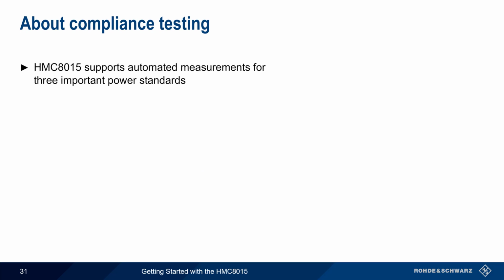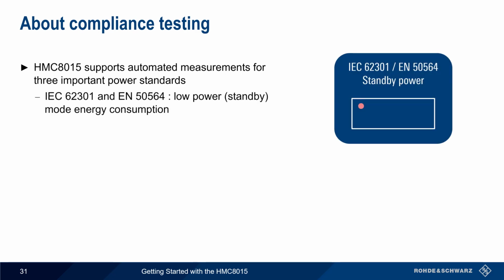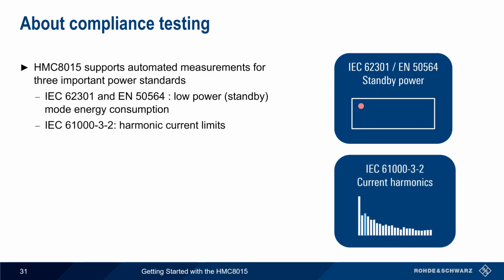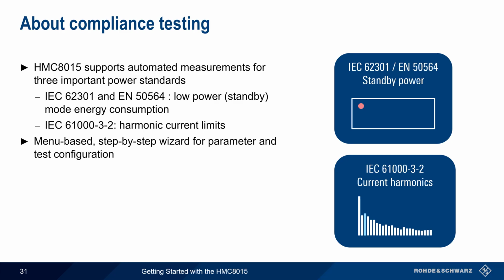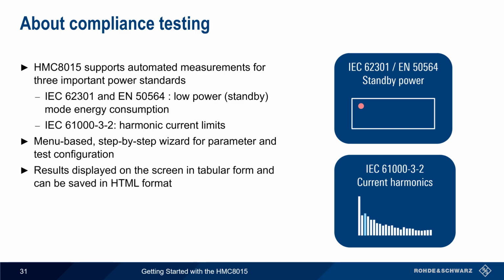The HMC optionally supports automated measurements for testing compliance to 3 important power standards: IEC 62301 and EN 50564, which measure energy consumption in low power or standby mode, and IEC 61000-3-2, which verifies the level of harmonic currents. These compliance tests are implemented as menu-based step-by-step wizards, which prompt the user for parameters and test configuration. The tests run automatically, and results can be displayed on the screen in tabular form and can also be saved and exported in HTML format.